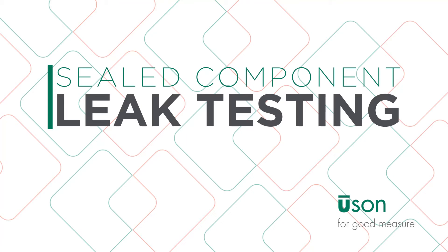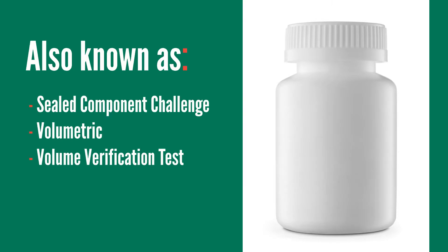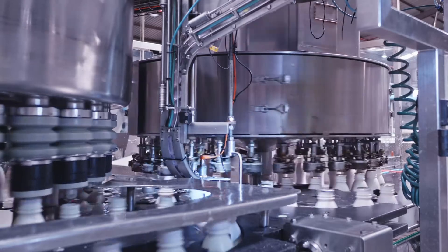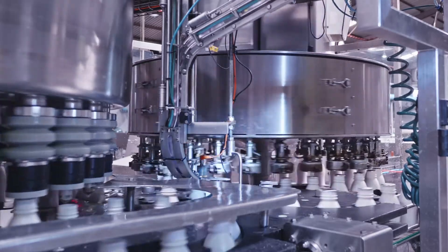Sealed component leak testing, also referred to as a sealed component challenge, volumetric or volume verification test, is used to test parts that are sealed and have no ports or openings to depressurize, such as pill bottles.